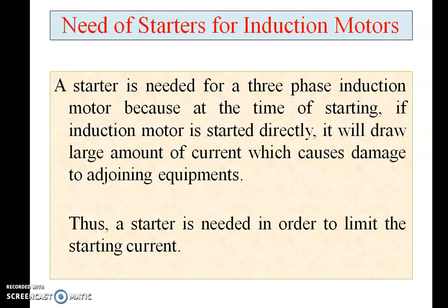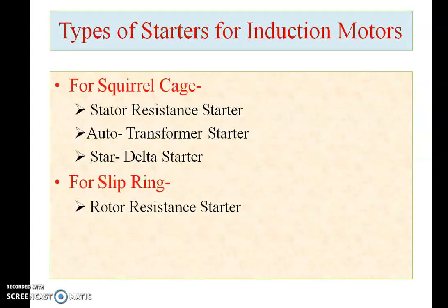unity slip as well as the low resistance of the stator winding, the motor will take heavy current. This heavy current will damage the different equipment of the induction motor, and it will also draw heavy current from the supply system, so the devices connected to that line are also badly affected. Hence, to avoid this huge starting current, we use starters.